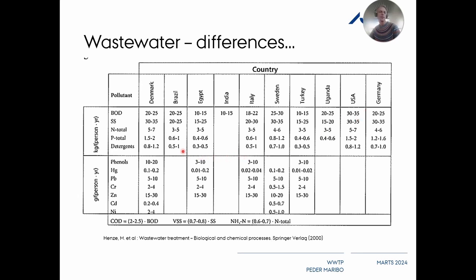In Denmark we typically discharge 1.5 to 2 kilograms of phosphorus per person per year, whereas in Sweden — a normally similar country — they are down to approximately half that level. One explanation is that Denmark has quite hard water with a lot of calcium and magnesium, so detergents containing phosphorus are needed to manage water hardness in laundry. Sweden uses a lot of soft surface water and doesn't need the same amount of phosphorus in detergents. There are interesting differences from country to country, so it's very important to look carefully into what we've got in the wastewater before designing our treatment plant.